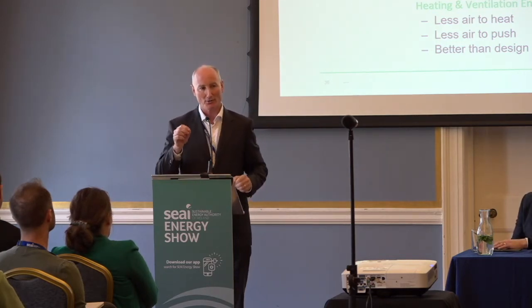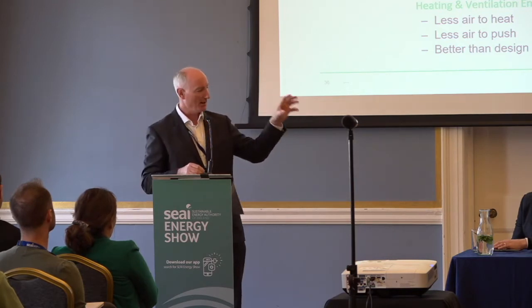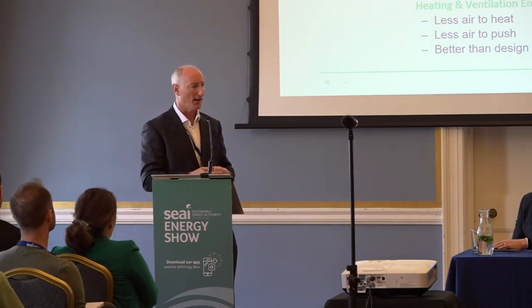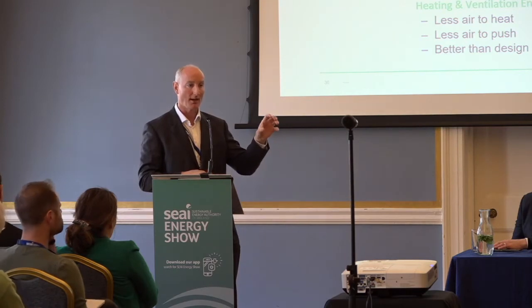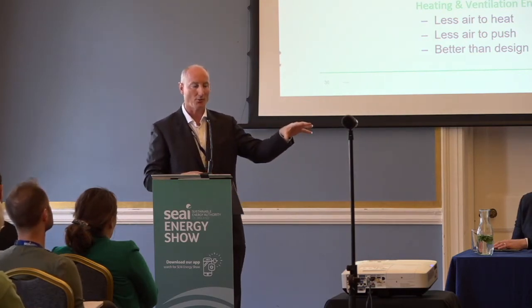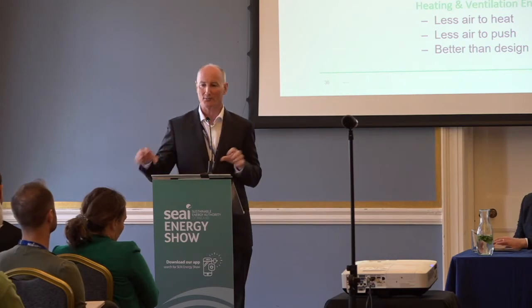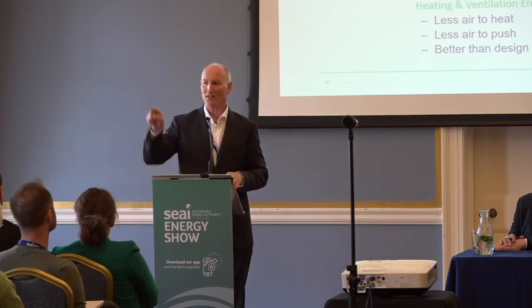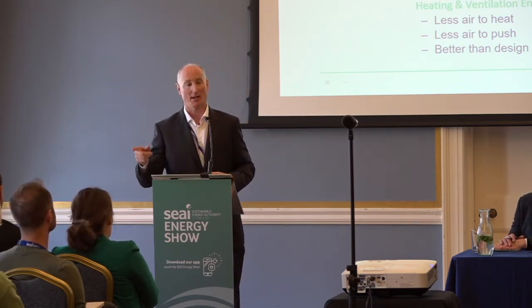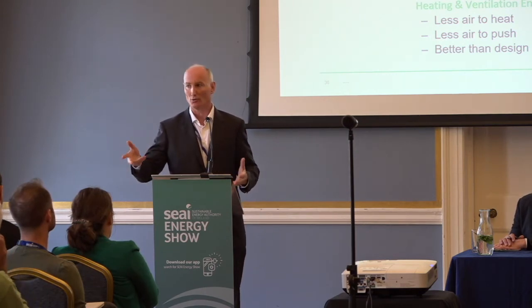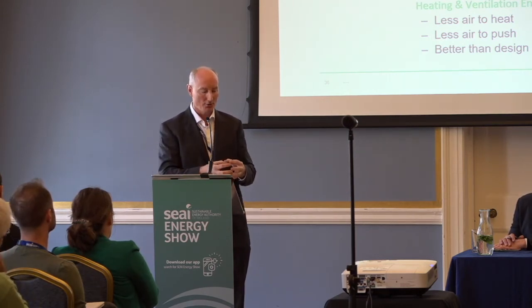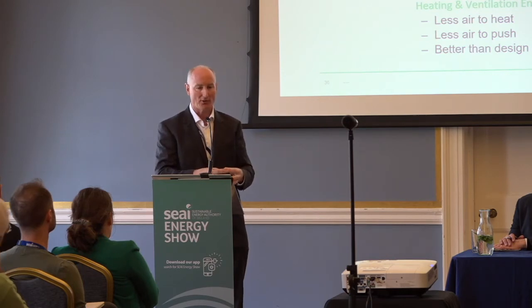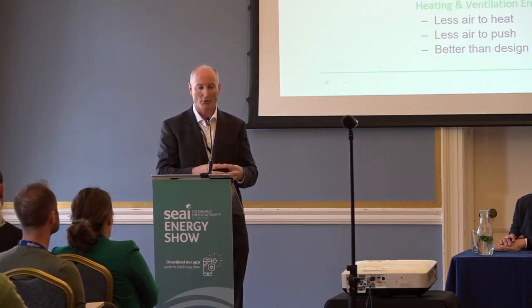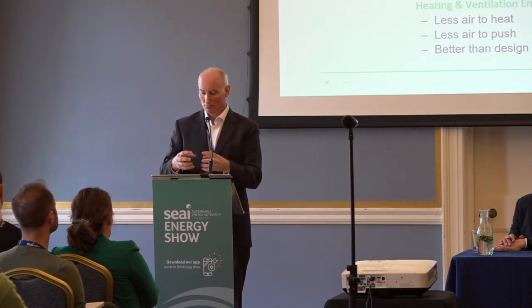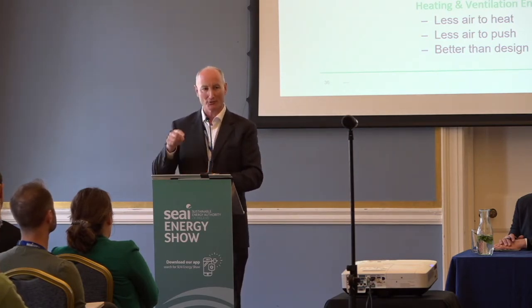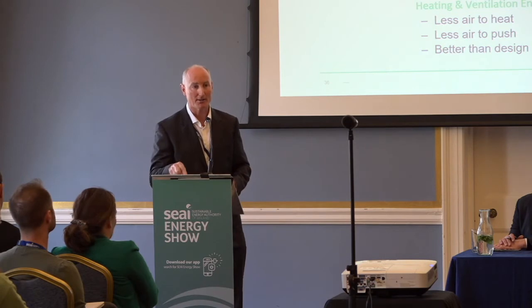So the micro solution is to have an indoor air quality sensor, a multi-sensor, that is tracking that CO2 in particular, but other factors as well, to know where the air demand is. And it's one thing to have the sensor telling you you're okay or you're not okay. Then what do you do when it's not okay? Do you have to go and open a window or leave the room? No, you want your multi-sensor, your intelligent sensor, to measure, of course, but also to control the local device that's responsible for delivering the air that you need, automatically.